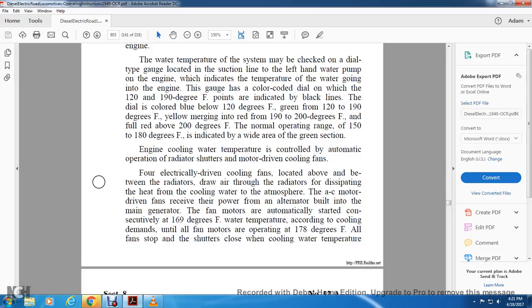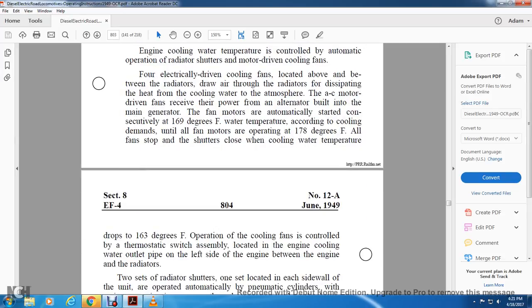Four electrically driven cooling fans located above between the radiators, drawing the air through the radiator, dissipating the heat with the cooling water of the atmosphere. The AC motor driven fan receives power from the alternator built with the main generator. The fan motors are automatically started consecutively with 169 degrees water temperature according to cooling demands. All fan motors operate at 178 degrees Fahrenheit. All fans stop and shutters close whenever the cooling water temperature drops to 163 degrees.